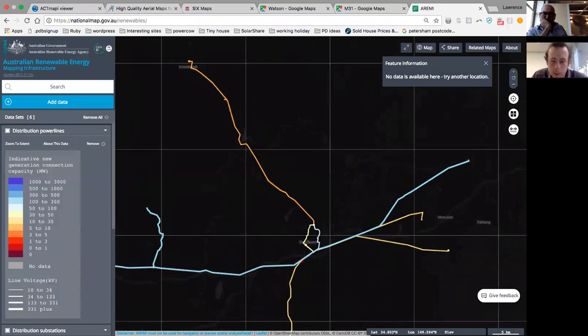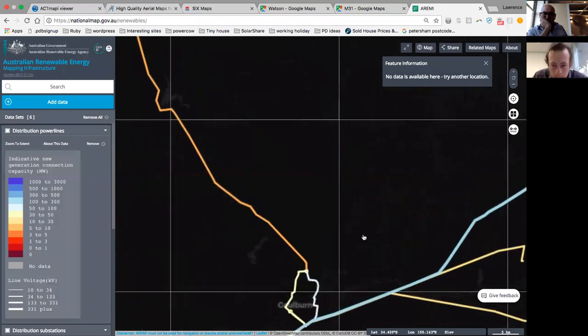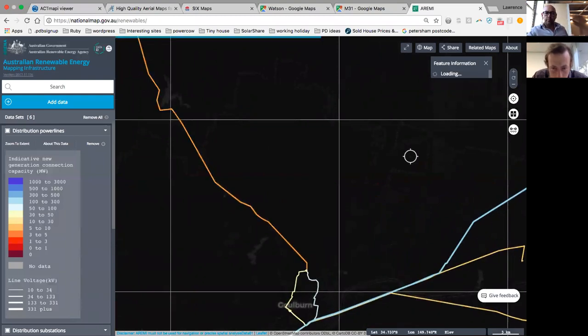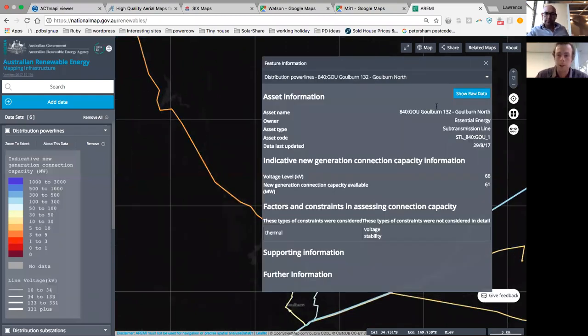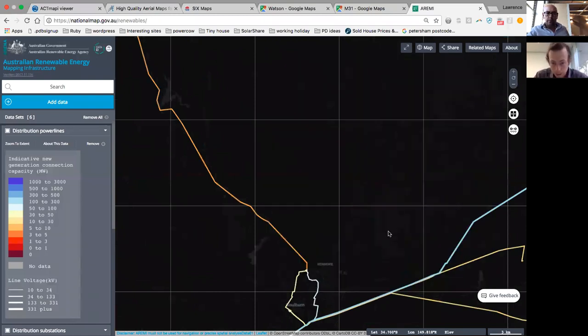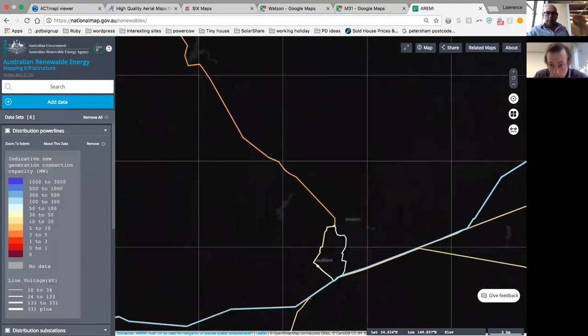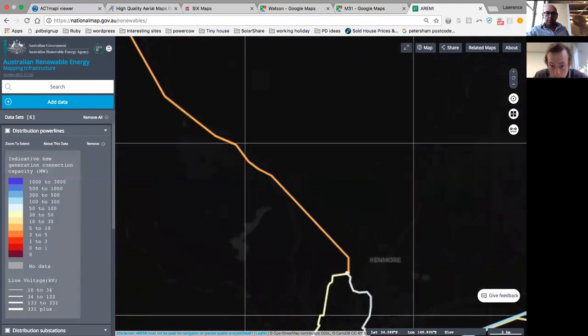The very thick ones, probably not so good for a 1 megawatt connection. These thinner ones, your distribution feeders, could be quite promising. I think this is a 33 kV line, if I'm not mistaken. Just clicking on it brings up detailed information. It's actually a 66, with 61 megawatts of capacity. That's not bad if you've got 61 megawatts you're hoping to deploy.